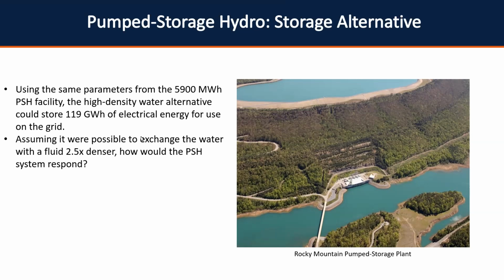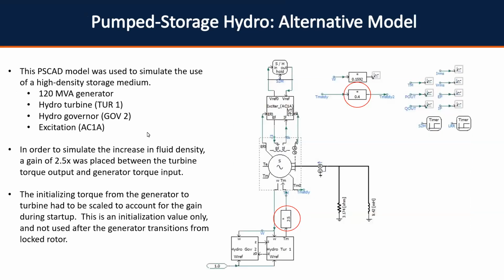What I wanted to do is model it to see how the turbine generator governor would respond if we increase that fluid density. So here we've got a PSCAD model. It's a 120 MVA generator with a hydro turbine, hydro governor, and exciter. In order to simulate that increased fluid density, I put a gain of 2.5 times on the torque output of the turbine to the generator.